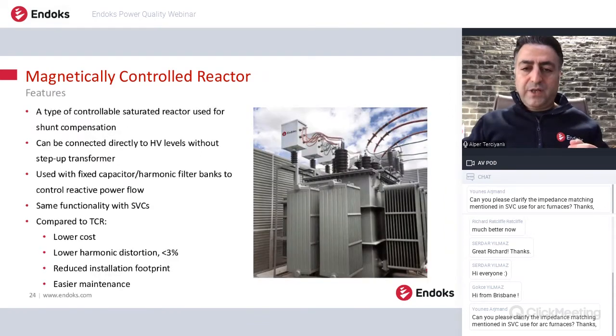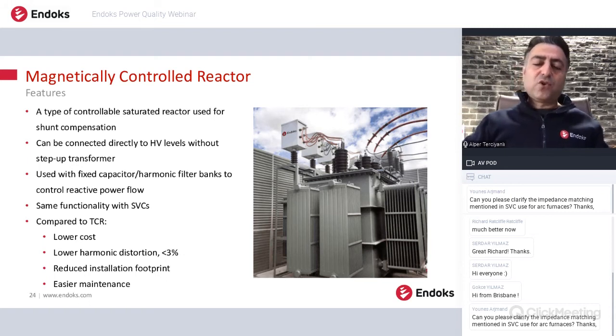I would like to show here. Yes, you see the photo. It's a typical oil-filled reactor, but we have thyristors on top of this reactor, and you see the connections between the control winding and the thyristor. So if we trigger these thyristors at the right time, we can inject a DC current into the core. So the core saturates, and the impedance of the reactor changes, and of course the output reactive power is changing. So this is a very compact solution.